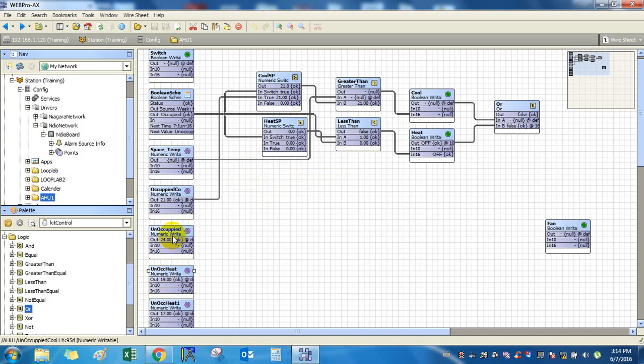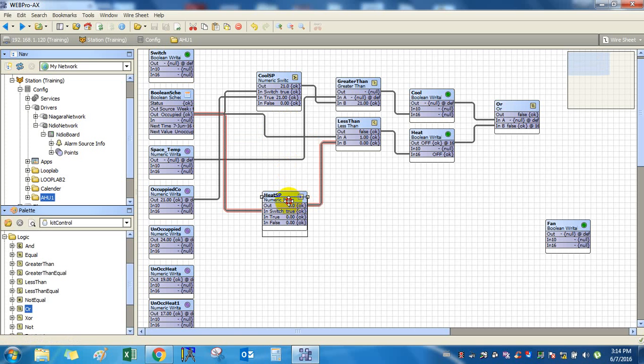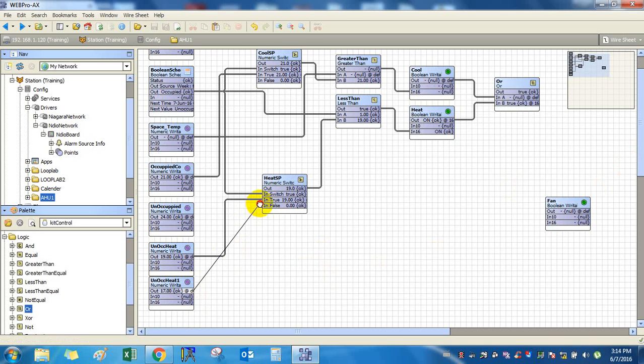So this logic will tell you whether you want cooling or heating in your space and when your fan should be running. Now let's have a damper. For that you need a numeric switch. You can duplicate this numeric switch and name it as damper switch. So whenever your fan is running, you have to open your damper. Link the out from this OR block to your damper switch, in switch, input.